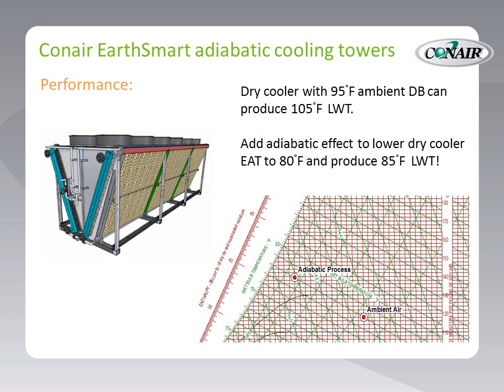If you remember the fluid cooler design, we were producing leaving fluid temperatures 10°F above the ambient dry bulb condition. The adiabatic effect of the EarthSmart tower utilizes wetting of the pads on the air inlet and, through evaporation of just the pad water, lowers the dry bulb temperature entering the fluid cooler coil. This creates leaving water temperatures that are much closer to those available in an evaporative cooling tower.